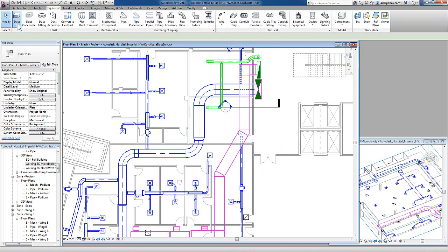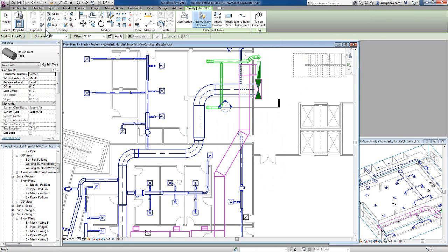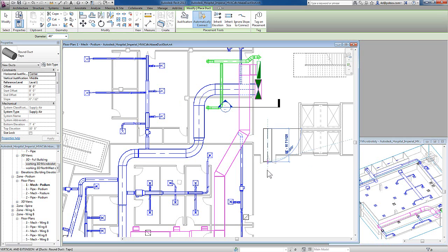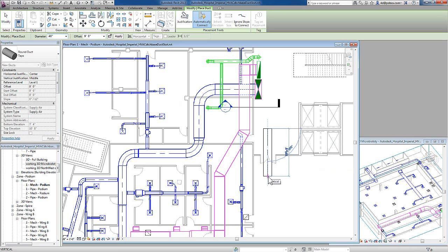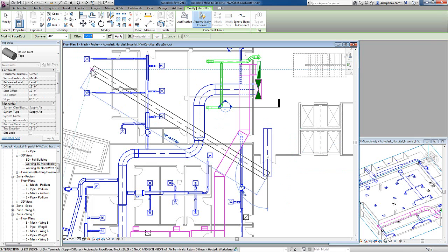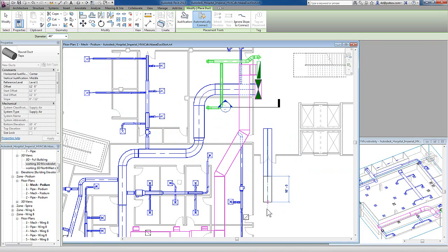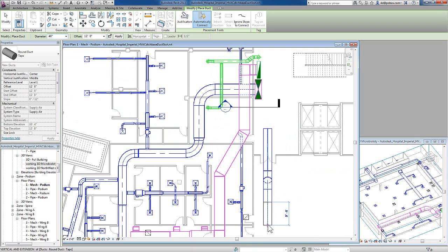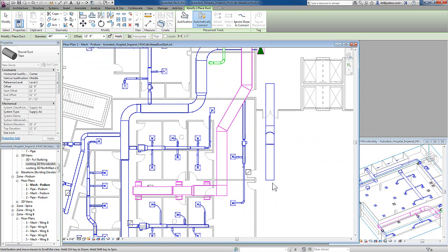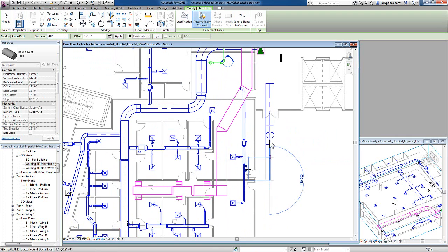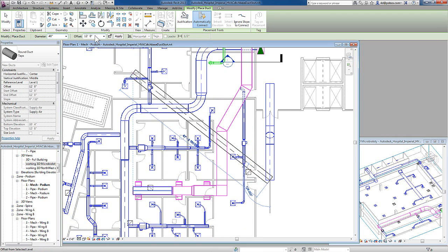So, I am changing elevations. I can create the duct and have it an offset. If I need to go up or down, I just simply change the offset on the options bar as I am adding the duct. I don't need to get out of the command and add another piece of duct. And Revit will provide the transitions needed to make that adjustment.